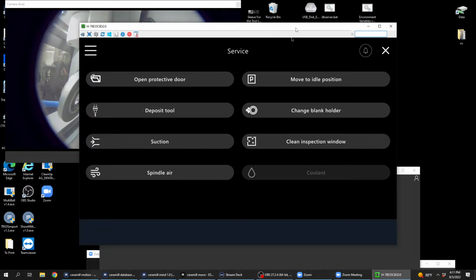It has the calibration pin, and we're basically in the midst of the calibration process. I'll make this full screen here. The machine will touch different points on the calibration objects. The calibration tool will make contact and close the circuit, and the machine, the software, knows where it's at.